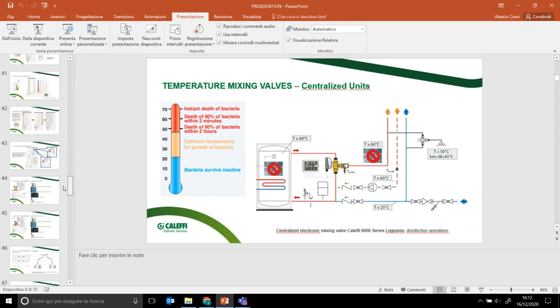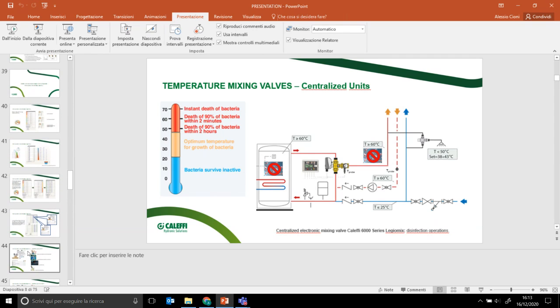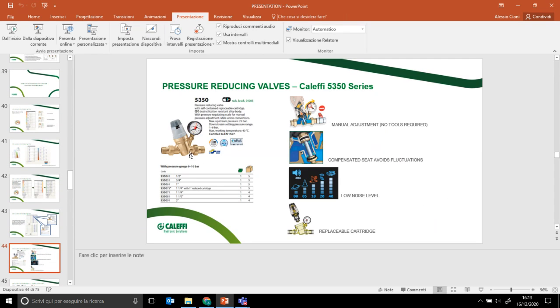Instead, the pressure reducing valve is a safety device reducing the pressure from upstream to downstream in order to regulate the flow rate to the final user. Okay, the final result is a regulation of the flow, but the operating principle is completely different. PICVs are using closed loops, PRVs are using open loops.